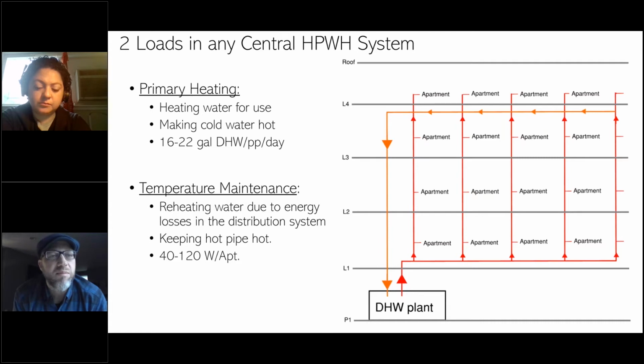We typically see between 16 and 22 gallons of domestic hot water per person per day. Really aggressive flow reduction and occupancy type will drive you closer to the 16, and the higher numbers we see in market rate. 22 is about what we see up in Seattle. So those are two data points. We've got some others as well. And then the temperature maintenance is another load.